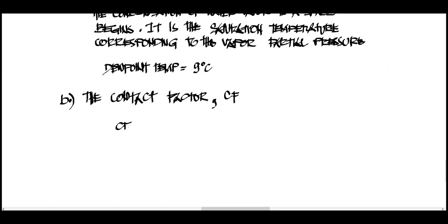So for the contact factor, we have your equation that will be T1 minus T2 over T1 minus the dew point temperature.